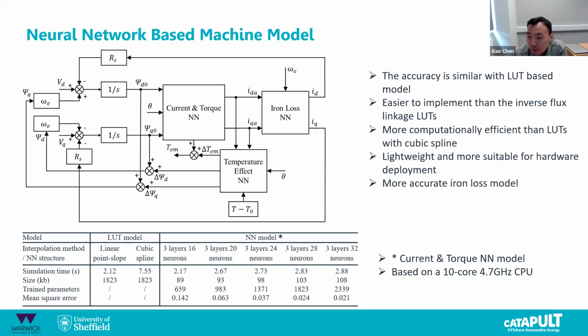And it's also lightweight and more suitable for hardware deployment, because you can see in the table the size of the model, the memory it needs is much less, because we do not need to store a lot of lookup table data in these neural network based models. And for the iron loss itself, we compared and found that it is more accurate as well. The simulation time we compared in the table is based on a recent PC, a 10 core 4.7 gigahertz CPU.